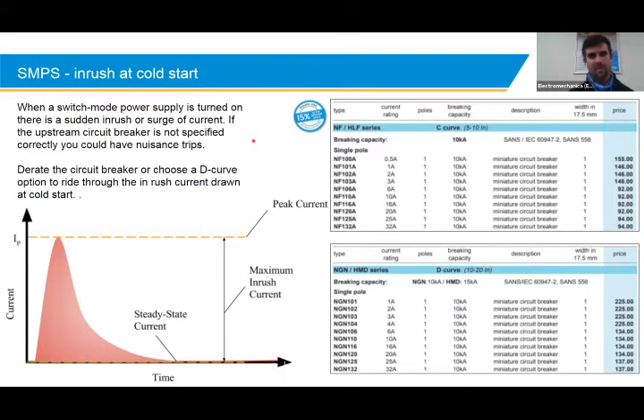I remember back in the day when I experienced these types of problems, couldn't really figure it out. But you would turn the breaker on and it would trip immediately. And the next time you turn the breaker on, it wouldn't trip because it obviously charged up a little bit the first time. So the second time you reset the breaker, it wasn't effectively a cold start anymore, as the caps would have a little bit of charge in them.